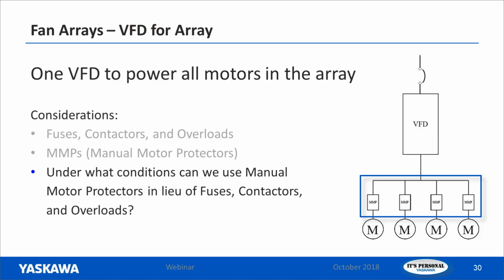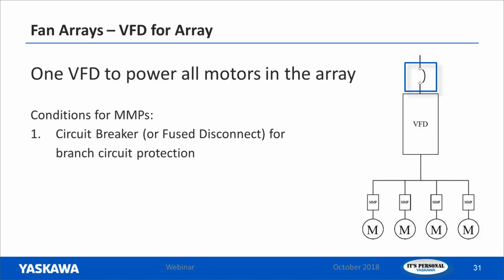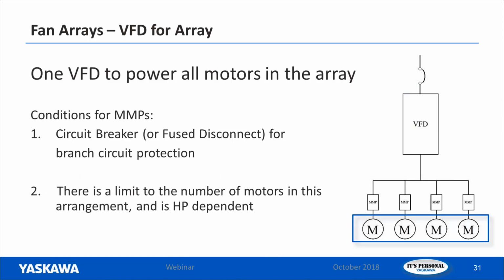So under what conditions can we use the MMPs in lieu of the fuses, contactors, and overloads? Well, number one, you do want to have a circuit breaker or fused disconnect upstream for branch circuit protection. And there is a limit to the number of motors in this arrangement, and it is horsepower dependent. So based on the horsepower, you can have so many motors and so on. We're not going to get into the details on that. That would probably be a whole presentation somebody could put together.